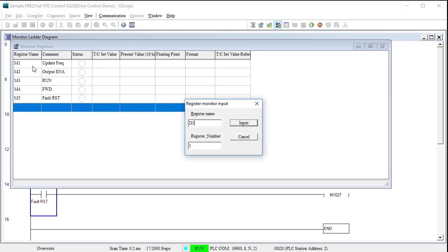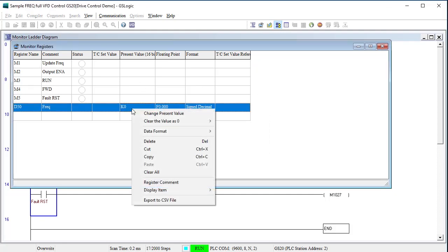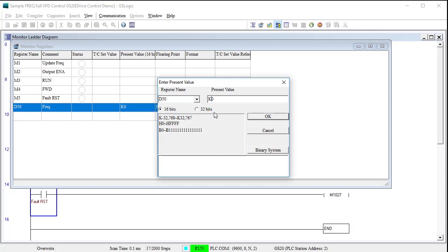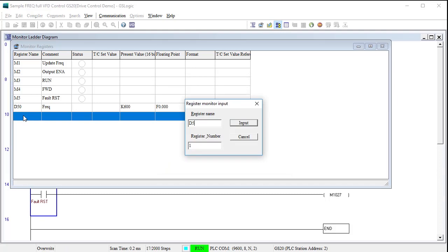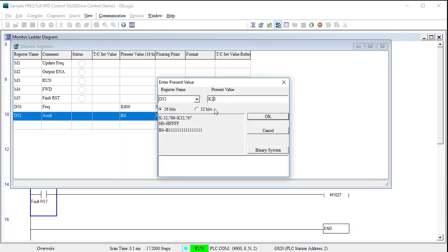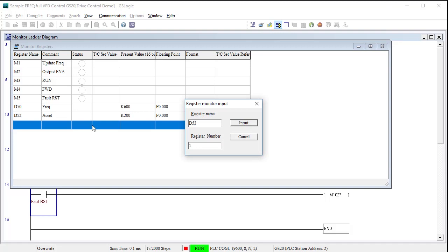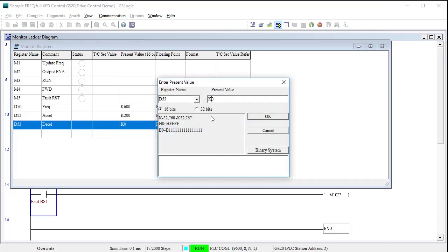I'll open a monitor window and add the M bit control registers starting at M1 and we want five total registers. We also need to set the D registers. Let's start with D50 which is the frequency register. Then right click to change the value. This tells you it is a 16-bit register and these are the formats we can use. We will use the signed decimal notation of K and we want 6 Hz which is a 600 because there are two implied decimal places. Hit OK and close that. Let's add D52 which is the acceleration and change that to 2 seconds. And let's add D53 and change the deceleration to 2 seconds.